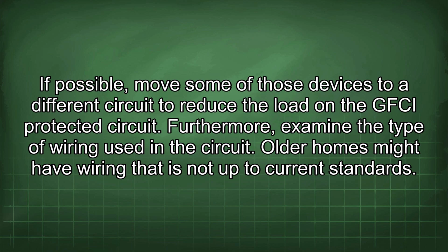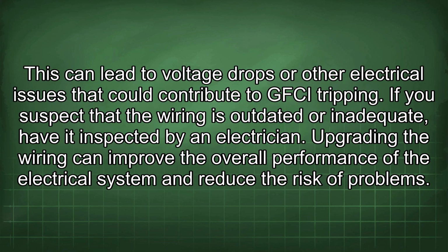Furthermore, examine the type of wiring used in the circuit. Older homes might have wiring that is not up to current standards. This can lead to voltage drops or other electrical issues that could contribute to GFCI tripping. If you suspect that the wiring is outdated or inadequate, have it inspected by an electrician. Upgrading the wiring can improve the overall performance of the electrical system and reduce the risk of problems.